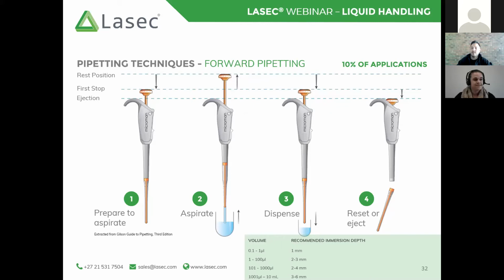Positive displacement pipettes are really great for that because the tips are also quite extended to accommodate that piston inside the tip. So unlike a normal disposable tip, your capillary pistons are generally longer. They've got longer reach to get into those tubes.